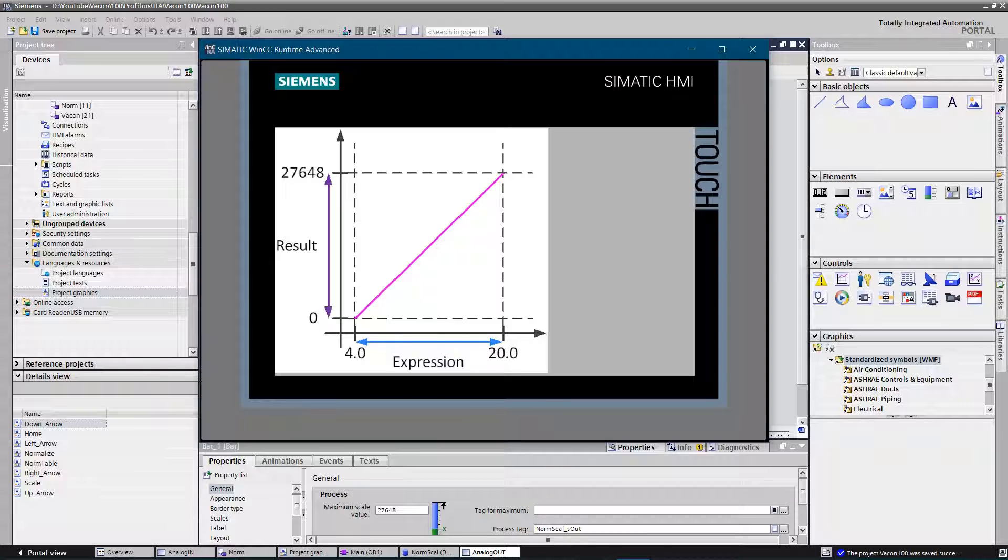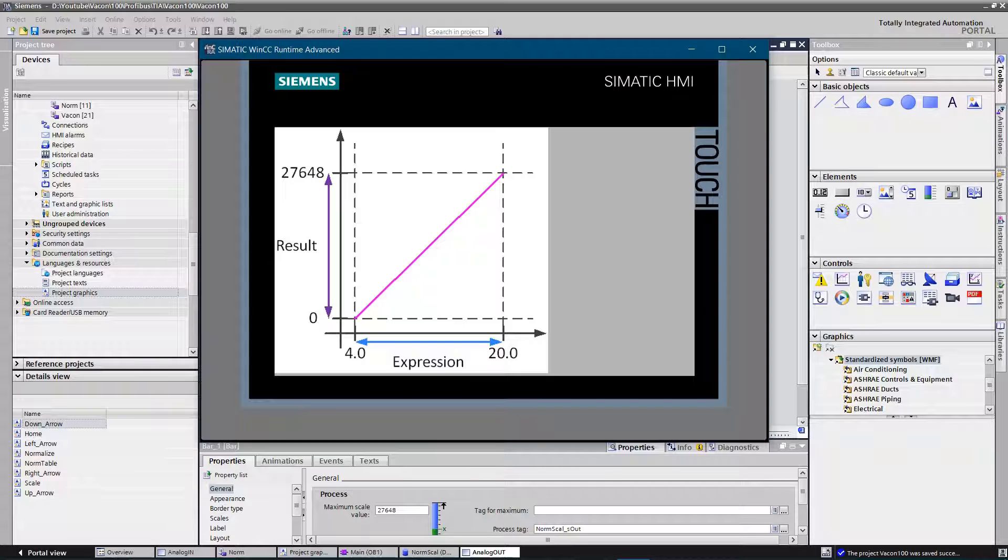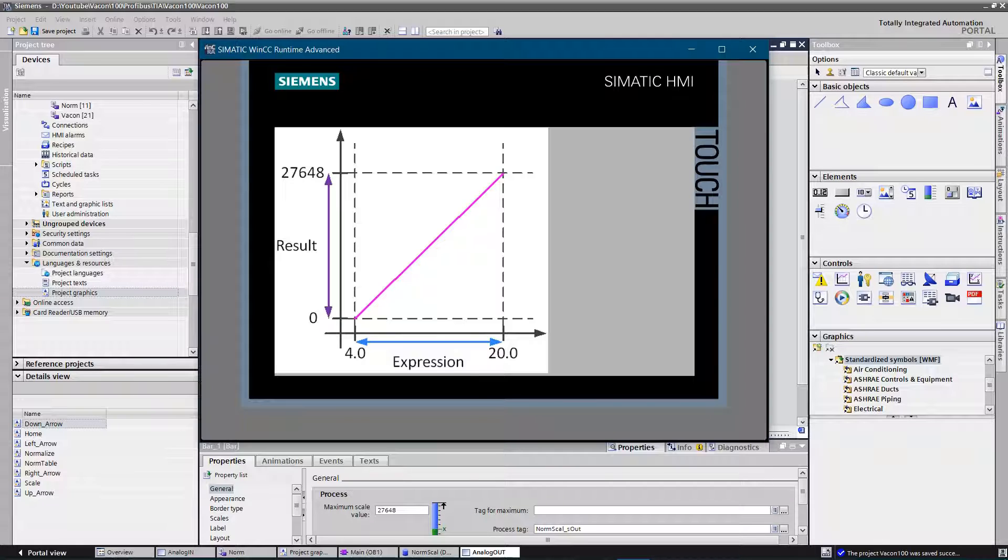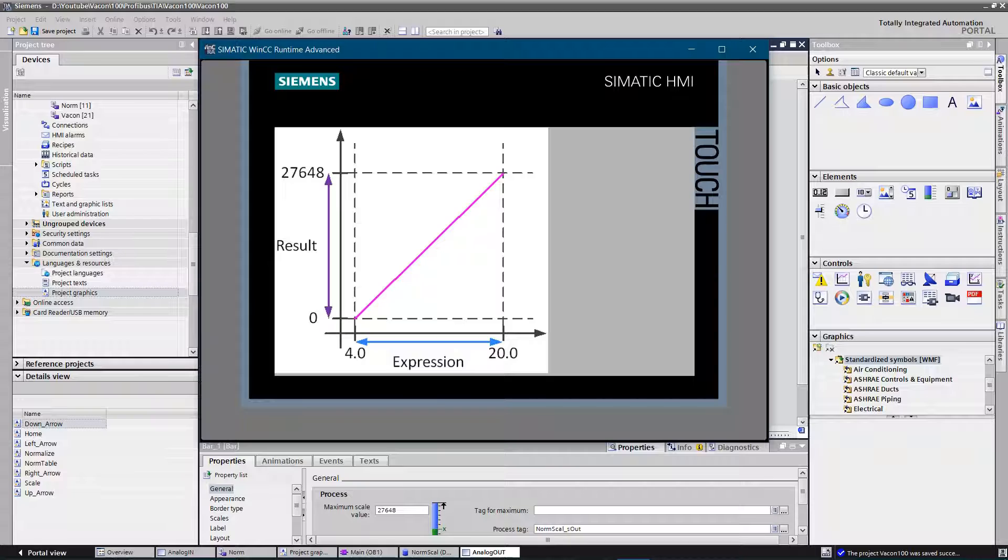Set points between 0 and 27,648 will be linear scaled within range of 4 and 20 milliamps. If you want to open valve by 50%, you need to set a set point of 13,824 and so on. Those values aren't very meaningful for the operator or the engineer, as you need to do math every time you want to change the set point.